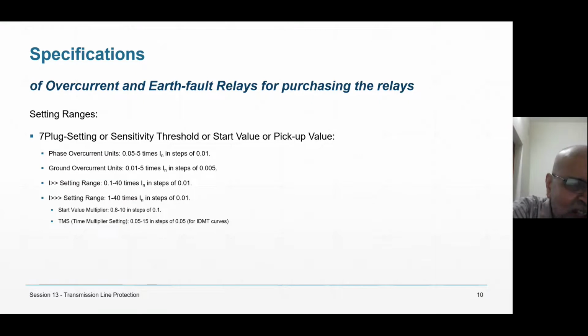Then there is I double greater than, 0.1 to 40 times IN. IN means rated current, in steps of 0.01. And I triple greater than, 1 to 40 times IN in steps of 0.01. Start value multiplier. This is a very important function. Once I explained that when you energize the transformer, it takes 10 times the current, but it is normal current and the transformer is not damaged. But if there is an internal fault, it can be 5 times, and then the transformer is very badly damaged.